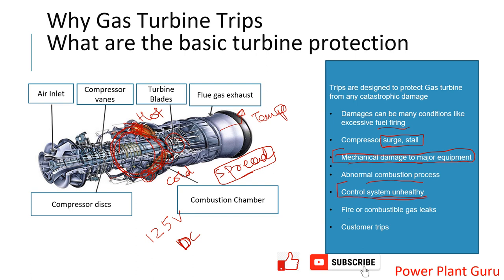Next is fire or combustible gas. A gas turbine is divided into different compartments — there is a turbine compartment, accessory compartment, load gear compartment, and others. In any compartment, if there is a fire or a fuel gas leak, it will be detected, the machine will shut down, and the fuel will be cut off.